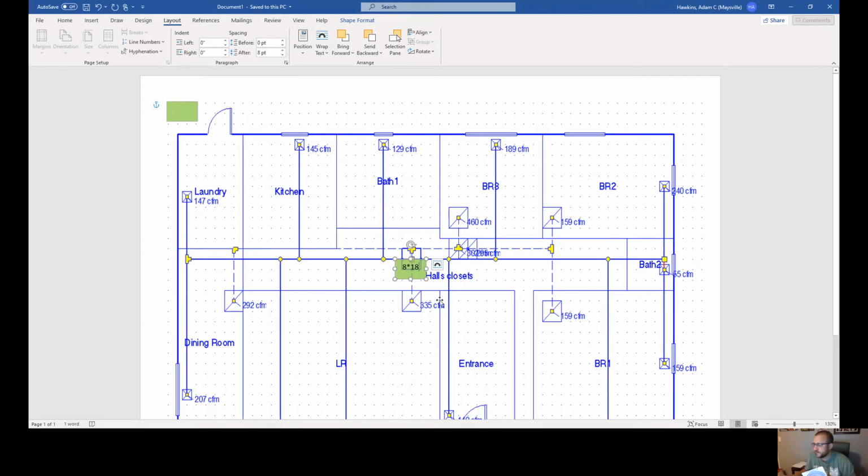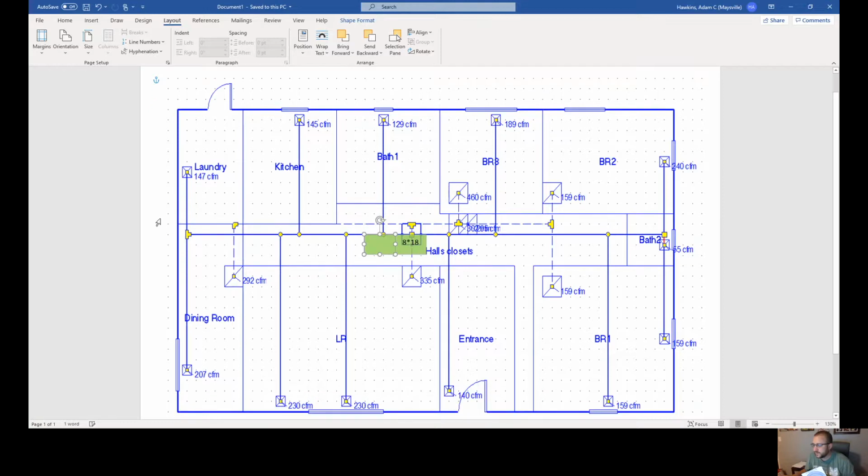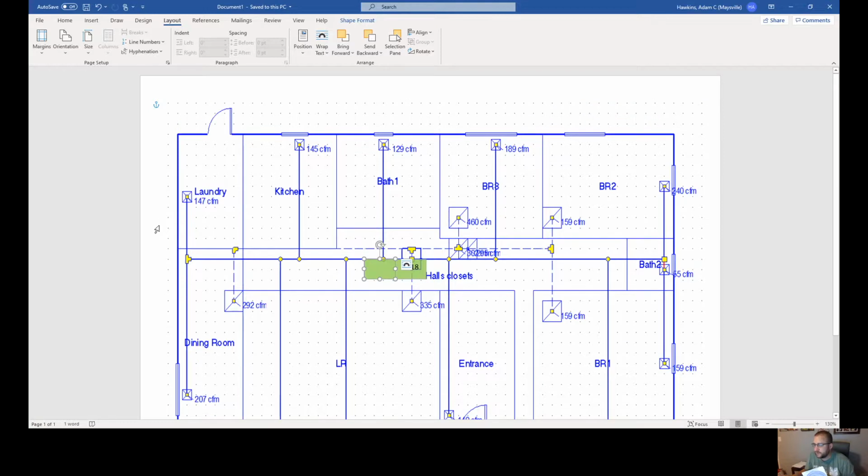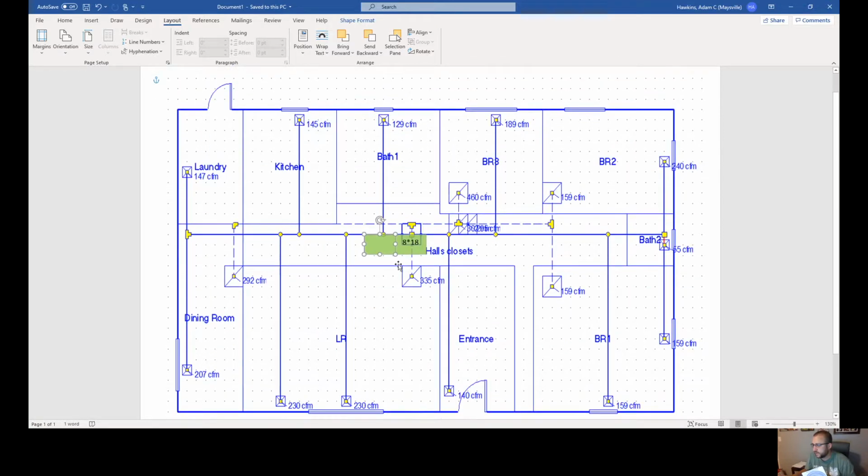All right, so then the next piece, I'm going to go to the left. I'm going to go to the north. So going north, the next 4-foot piece has to be big enough to carry everything on that side. All right, so in this case, now granted, we only have 800 available, and this is going to be way over that. So I'm going to have to kind of change some of these numbers a little bit.